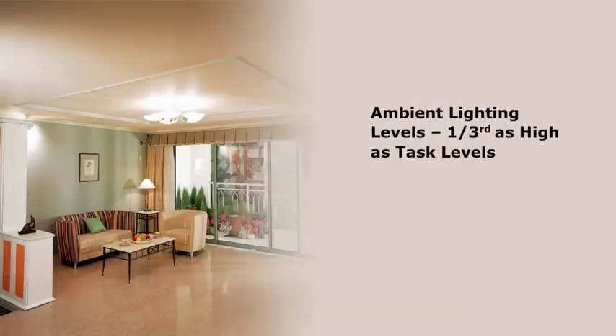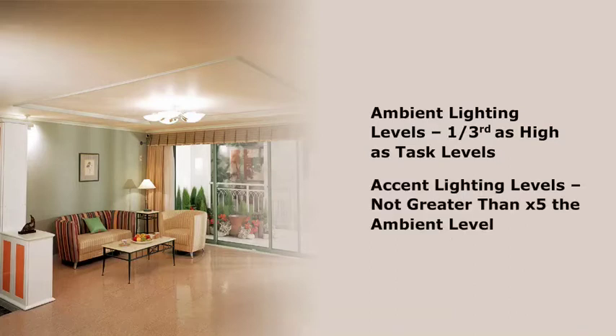Ambient lighting levels for general lighting should be at least one-third as high as task levels. Accent lighting levels that provide focus on a specific object should not be greater than five times the ambient level.